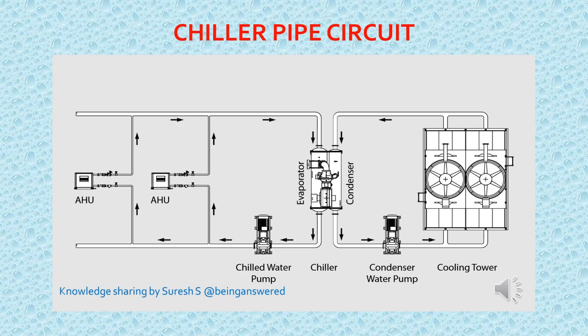If you see the chiller, there will be two parallel pipes running into it. Water from the cooling tower will not go to the AHU room, so there are two different circuits. Inside the chiller, only heat exchange will happen. Heat from the space where we need air conditioning will be absorbed by the chilled water, and that will come to the chiller. From the chiller, that heat will be transferred to the other circuit, in which water circulates from the cooling tower to the chiller. So the chiller acts like a heat exchanger, absorbing heat from one place and transferring it to the other circuit, and that heat will be emitted into the atmosphere through the cooling tower. I hope this circuit gives a clear understanding of how the chiller works.